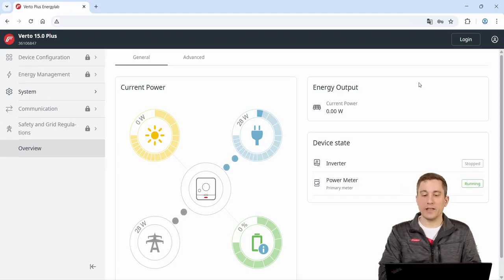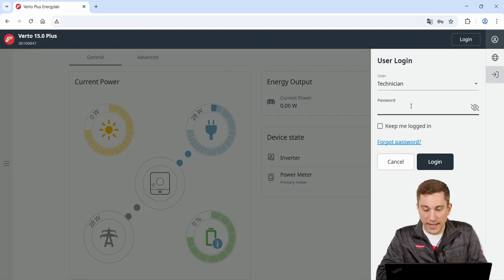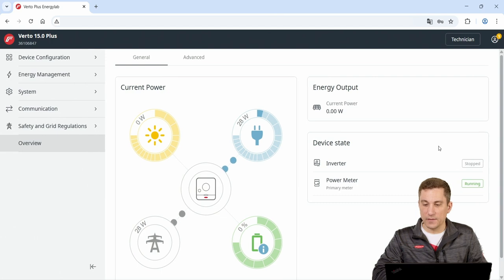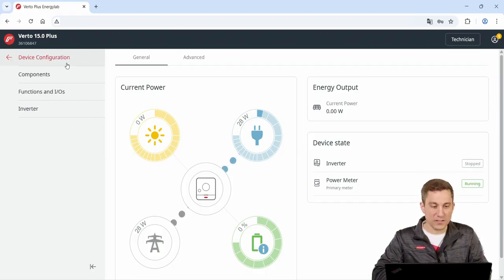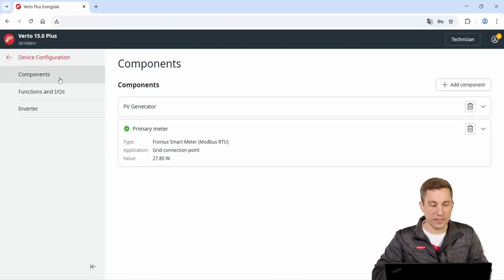First step is to log into your account. Please note that you will hit the login button on the right top of the page and then choose the technician user. Please note that only authenticated personnel can do this and you need to have the technician password to log in. This password was given by the installer for the first initial commissioning of the inverter. After that, you gain access to the so-called device configuration in the settings. This button you can hit and then you hit the point components.